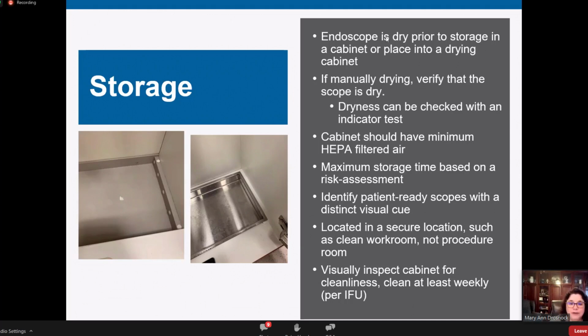We kept the recommendation to have a distinct visual cue on your endoscopes so that anyone or I can walk into your room where your scopes are being stored and see visually that they've been processed. So that recommendation we still have in there as a should. Making sure our cabinets are located in a secure location, like a clean workroom, and not the procedure room. And I see that a lot in the ambulatory settings where the storage cabinets are right in the procedure room, that we should try to move if we can. And making sure we're cleaning the cabinets at a regular interval, at least weekly. Most facilities are doing weekly, some are doing it daily. But inspect your cabinets too.